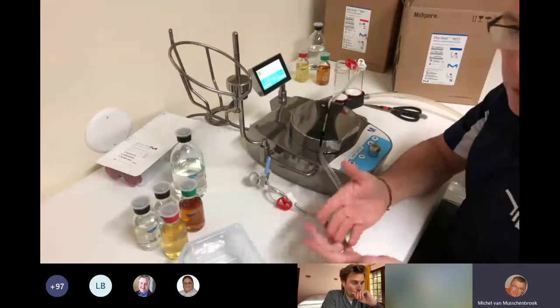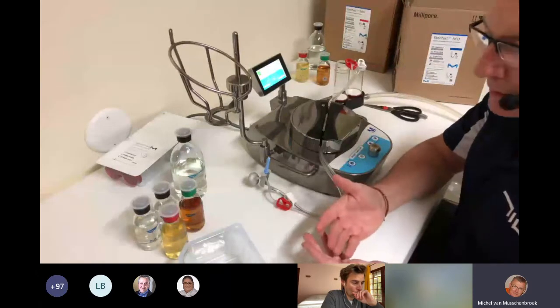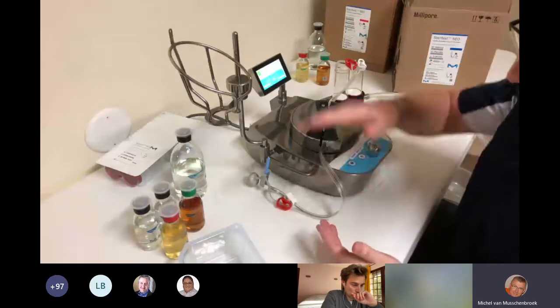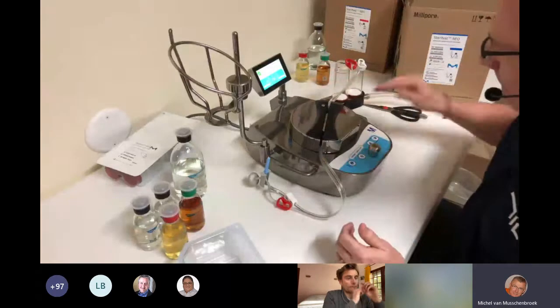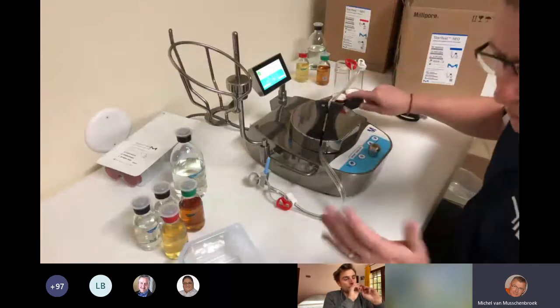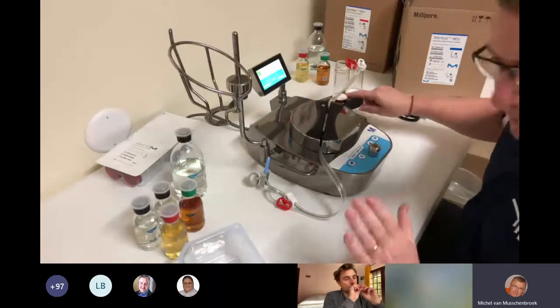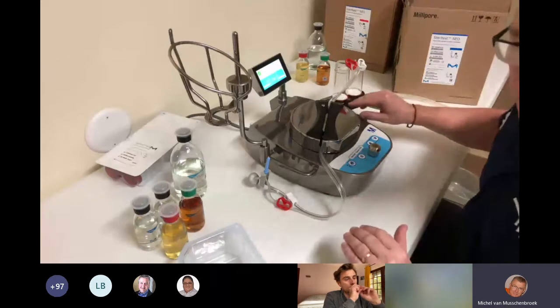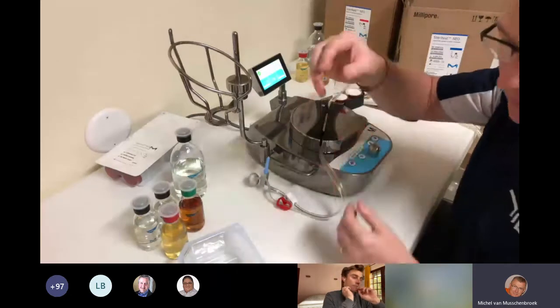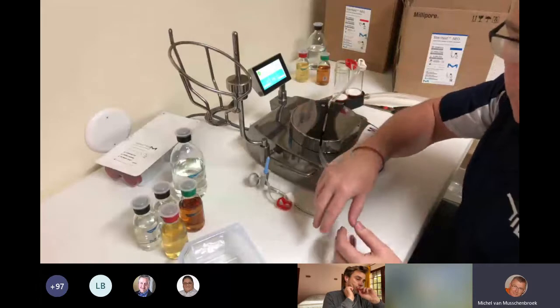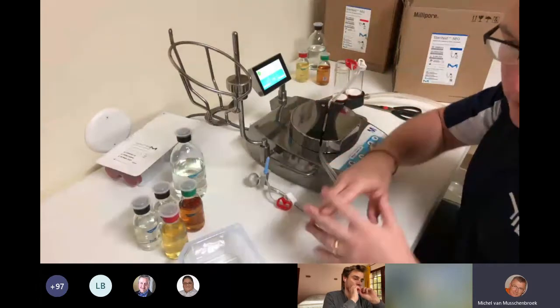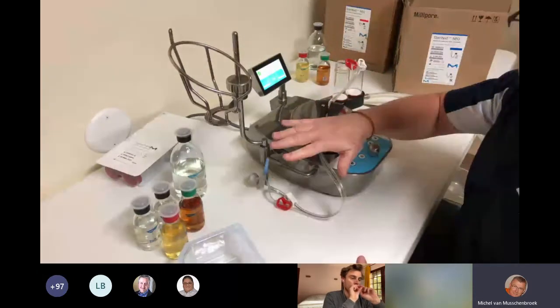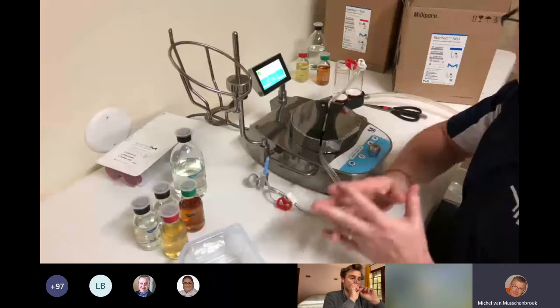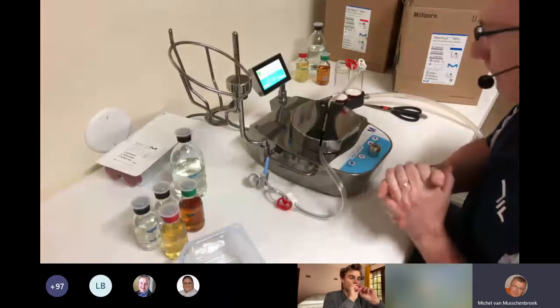When the sponge is hard and dry, it doesn't absorb as well. Same idea for a membrane - we want to prepare it. Now, in the event you were doing a very small sample, when you run your pre-rinse, we'd recommend you stop before you've completely finished, and that allows your product to come into the wetting solution and spread out over the surface of the membrane.